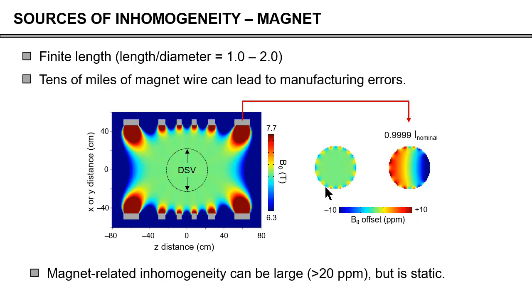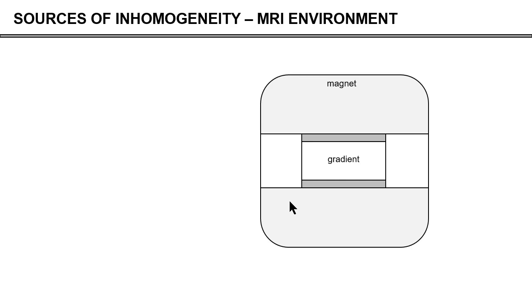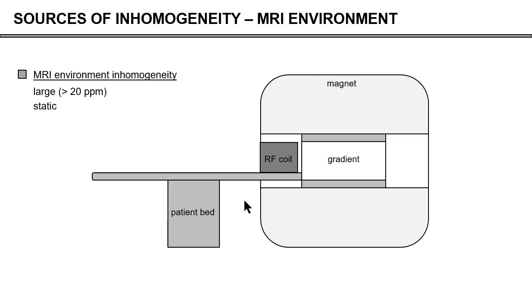Magnet-related inhomogeneity can be large, but fortunately it is typically static — it doesn't change over time. Other things that introduce inhomogeneity are the environment in which the magnet is standing and the stuff that we put into it. The gradient coil introduces some inhomogeneity, the patient bed moves and introduces inhomogeneity, and the RF coil and metal beams around the magnet all introduce some level of inhomogeneity. But again, those are also fairly static, and this requires a one-time compensation during the installation of the magnet.